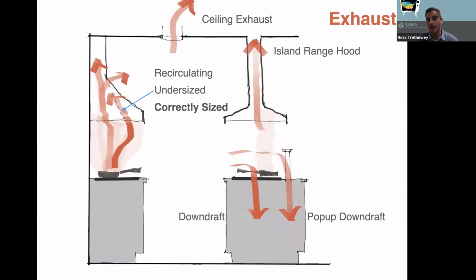So how do we deal with it? There's a lot of different ways that kitchen range exhausts are done. We try to highlight the ones we see the most. We'll start off with what I would consider to be the best way to do it, and that's with a correctly sized wall canopy hood. If you look on the left-hand side of the screen, a correctly sized hood is one that covers the full cooking surface and comes out to the front, over the front burners on the cooktop. And it's obviously venting at the right rate.